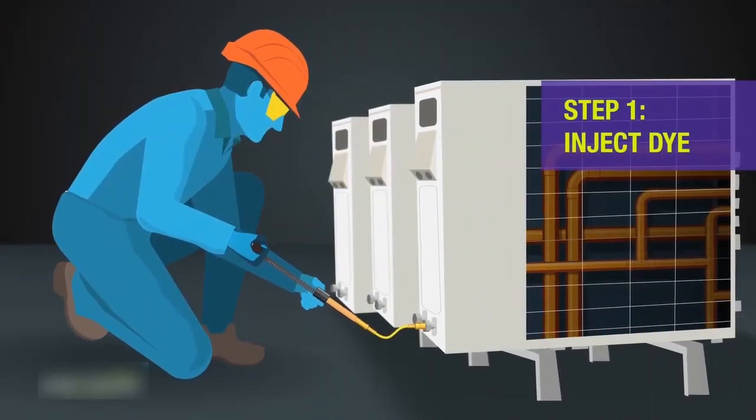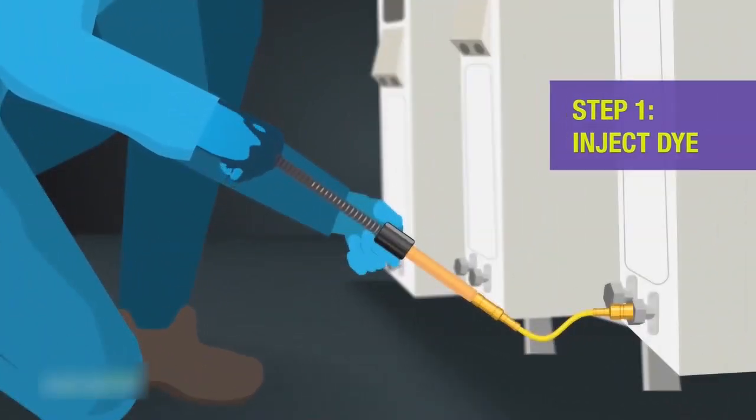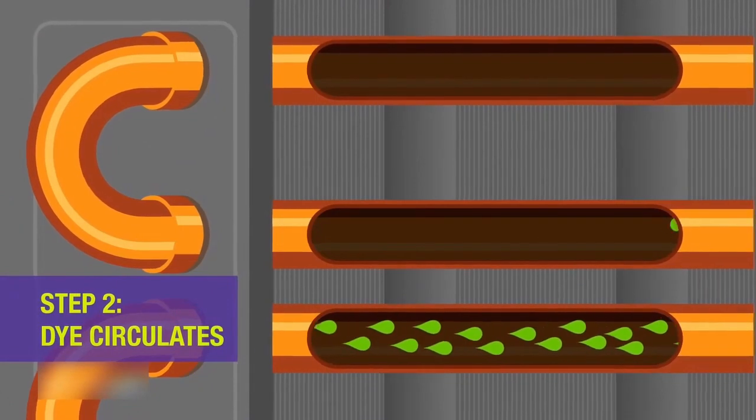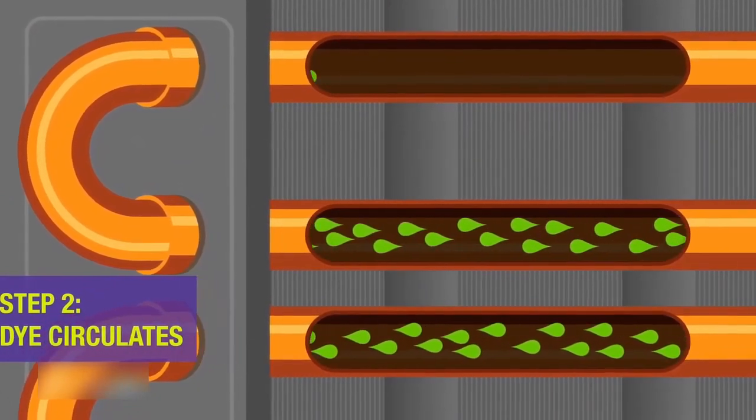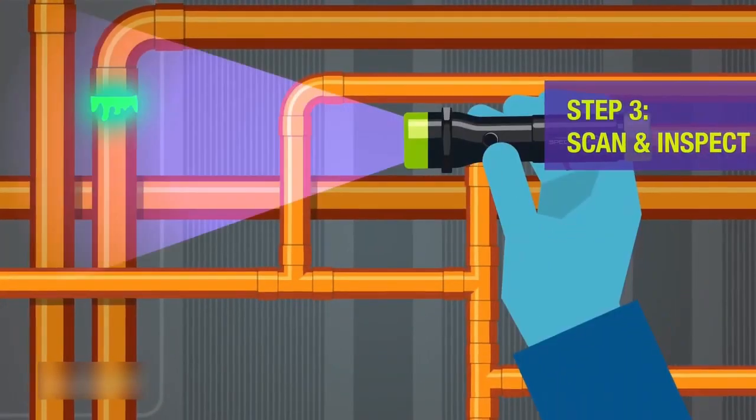The process is simple. The technician injects the fluorescent dye at the low side of the unit while the system is running. The dye starts to circulate throughout the unit. The technician then scans the system with a violet or UV lamp.